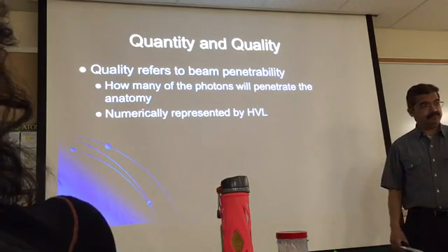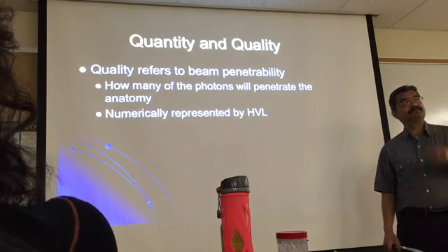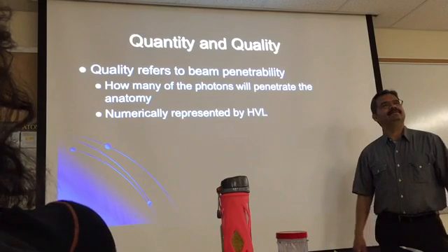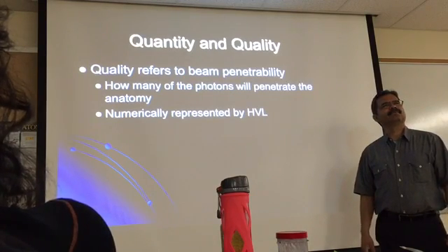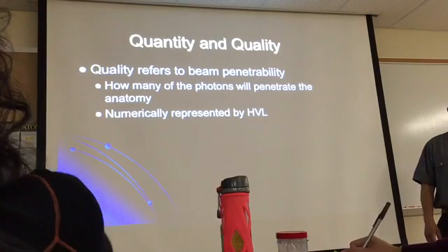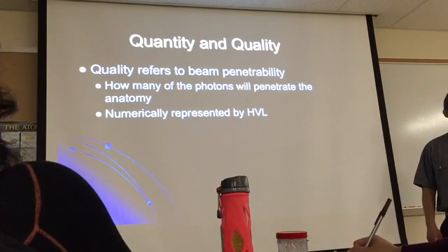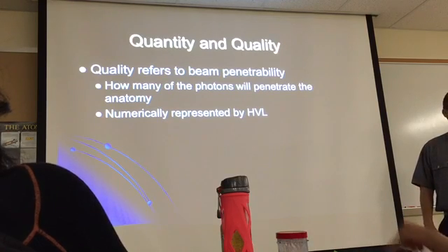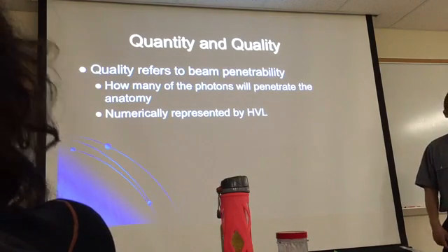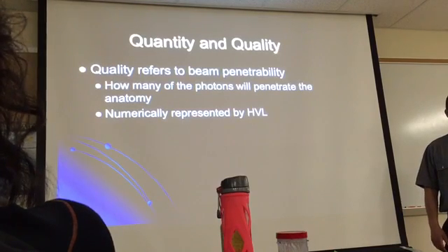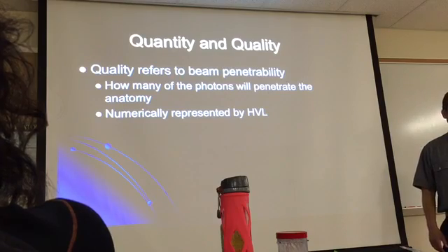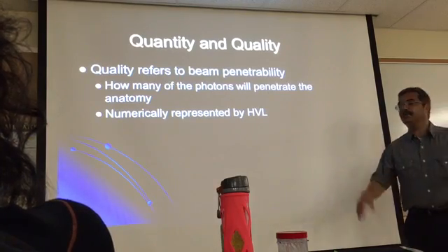You said 3.2, was it a lead equivalent or aluminum? For 80 kVp, 3.2 aluminum. I'm sorry, aluminum equivalent. Yeah, if it were 3.2 lead, we wouldn't allow anything to go through. Double checking. Aluminum, yeah. All right. Are we good so far? Is that making sense? Okay, good.